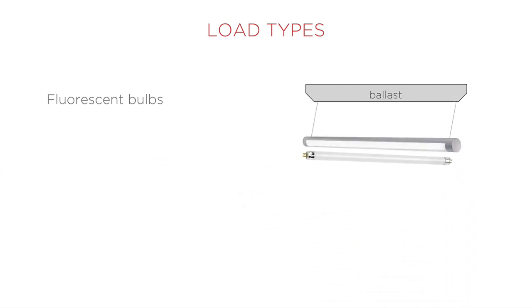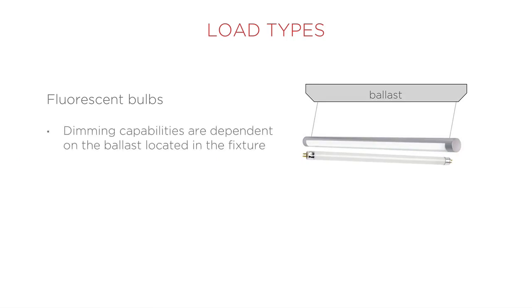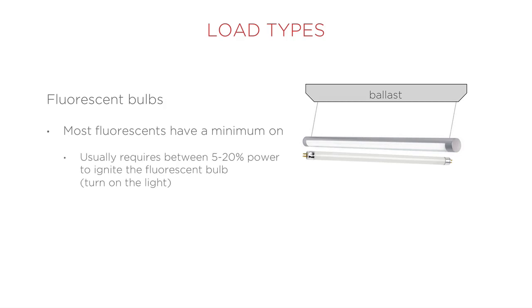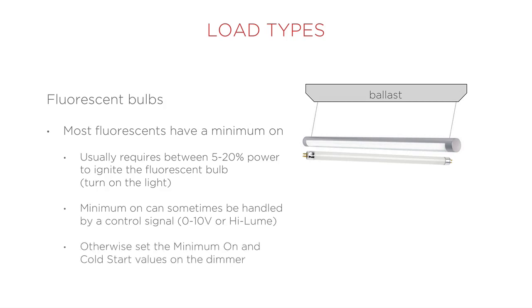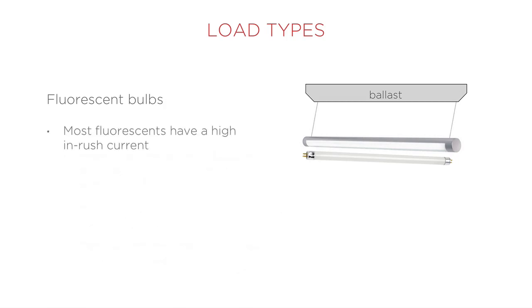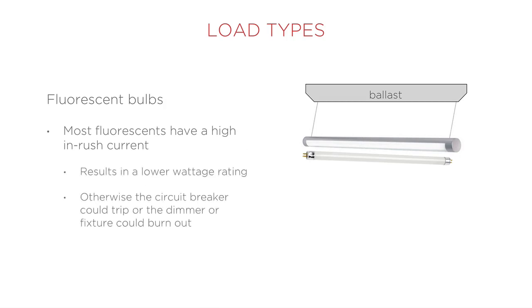Fluorescent bulbs are connected to a ballast within the fixture. Whether or not that fluorescent bulb can be dimmed is dependent on the ballast itself. Most of the inexpensive ballasts are not dimmable. Most fluorescent lights have a minimum level in order to ignite or stay on. That level is usually between 5 and 20%, which can be handled by a control signal with 0 to 10 volt dimming or Hi-Lume dimming, or can be managed by setting the minimum on and cold start levels within the Control4 dimmer. Most fluorescent bulbs have a high inrush current, which can result in lower wattage rating.